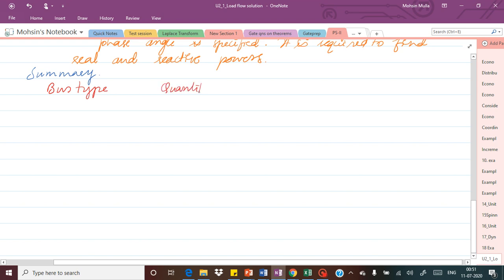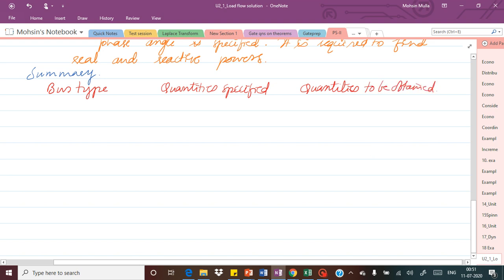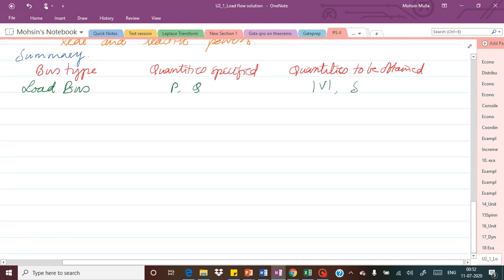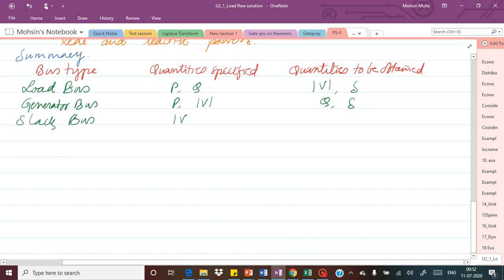To summarize: for the load bus, P and Q (real and reactive power) are specified and the voltage magnitude V and phase angle delta are to be obtained. For the generator bus, real power P and voltage magnitude V are specified and reactive power Q and delta are to be determined. For the slack bus, voltage magnitude V and phase angle delta are specified and real and reactive power P and Q are to be determined.